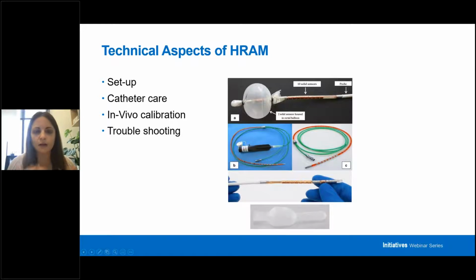If your catheter doesn't calibrate, the software will tell you something is wrong — you'll see little pinches instead of a solid block of color, so it's very easy to tell when it doesn't go right. There are a number of methods you can try, including a feature called tuning the system, where you can block certain corrupted sensor channels. Tech support for whatever company you're using can really help guide you through that.